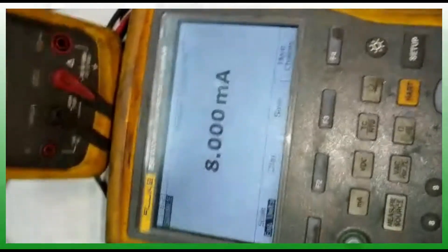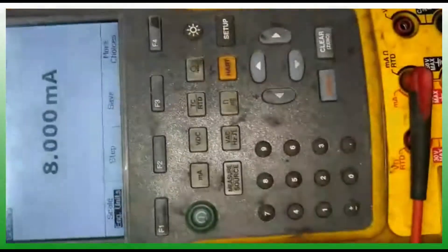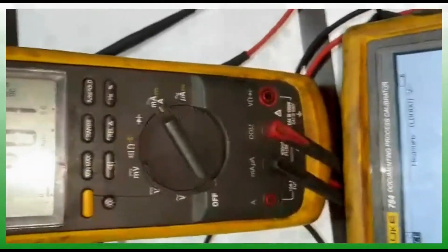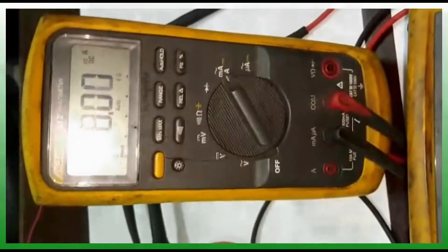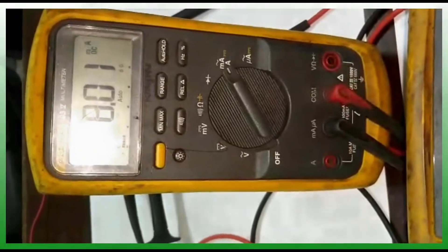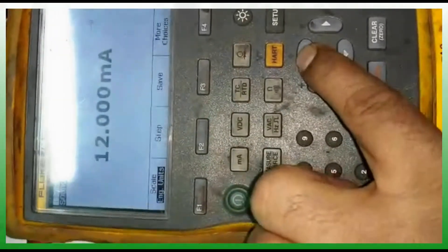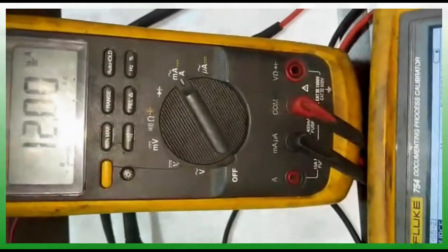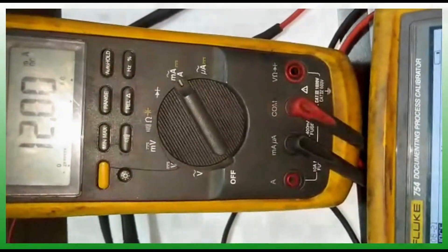4, 8, 12 like that. You can see here how many milliamps are given. That is the source which is coming from the source meter calibrator. From this source it is going to the multimeter. Now 12 milliamps, 12 milliamps output.